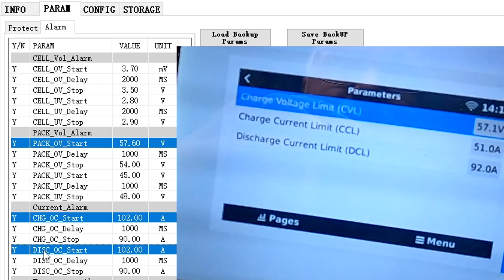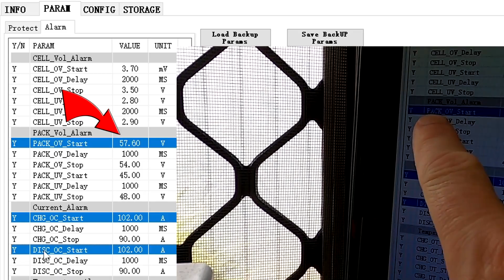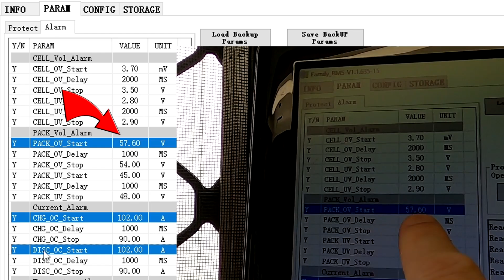These are the parameters of the BMS in the Victron system, if the BMS is connected via a type A cable, which I have done. You can see the charge voltage limit is at 57.1, and our charge voltage limit, or the pack over voltage alarm, is at 57.6. So this is exactly half a volt over what will be reported to Victron.